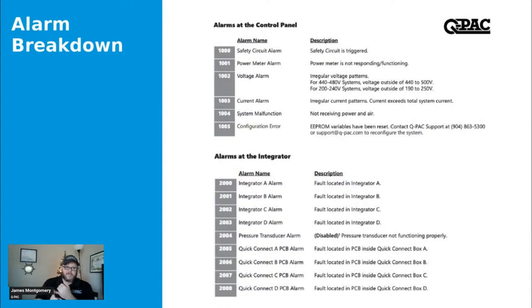The power meter, like I said, is inside the control panel. We're pulling legs of the voltage from the input. We've also got a CT. And so going into the next one, that current alarm, we're measuring current. If you're operating with an extremely low voltage, since voltage and current are inversely proportional, you would potentially have higher current. So either not having any current present would be an alarm, or if it's outside of normal parameters.